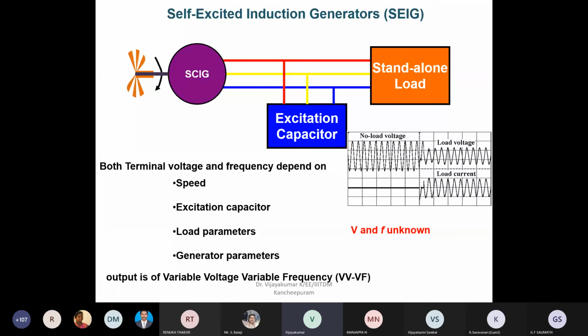So if you are going for a standalone system, I already told you, if you want to make your induction machine a generator, you need to provide the reactive power. So if you want to supply standalone loads, then you need to connect capacitor banks at the stator terminals. Then only the machine will be excited and supply the loads. If you are not connecting the capacitor banks, then it will not work as a generator. So the excitation capacitor is very important for supplying standalone loads by induction machines. Otherwise, it will not operate.